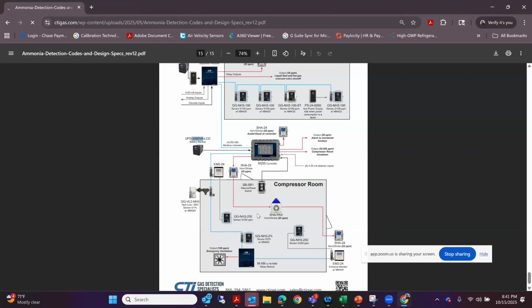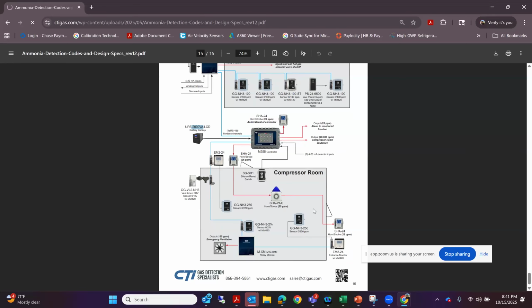If the fans stop, that's where it starts getting questionable, especially if you've got MCC buckets out here, or relays out here, which there never should be anything relay wise out there, but I know some places have. But as long as you're really moving the air, you're pretty safe. So my understanding was this setup is just to take the bounce out. When somebody hits an e-stop, that generator circuit kicks on, it starts feeding the power back to the safety equipment, and to the ventilation, and to keep maybe high priority goods that cost a lot, I don't know, keep them cold. I don't know what all goes on with that circuit. There's so many different things that it could be running in a facility.